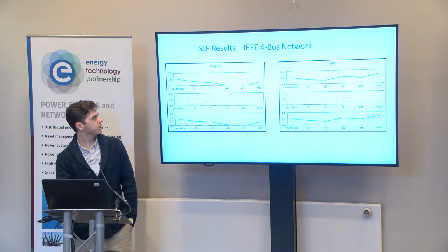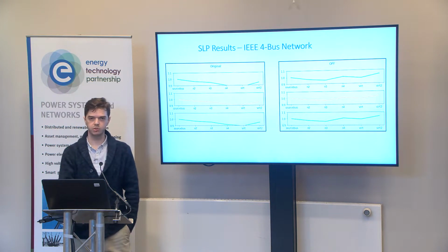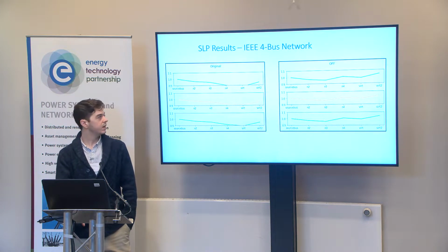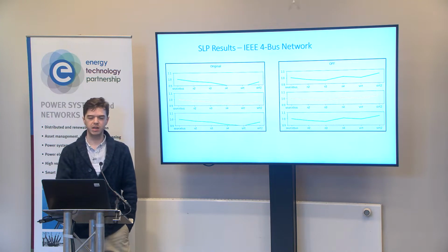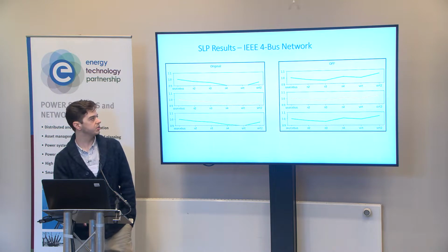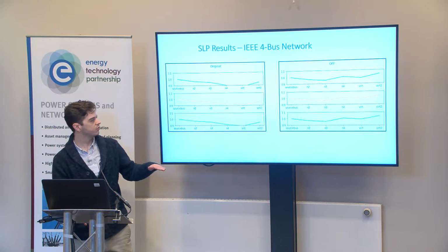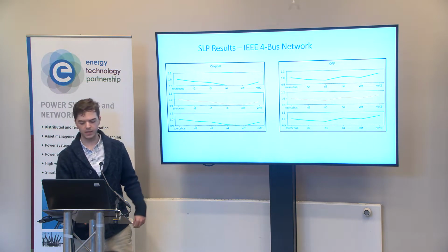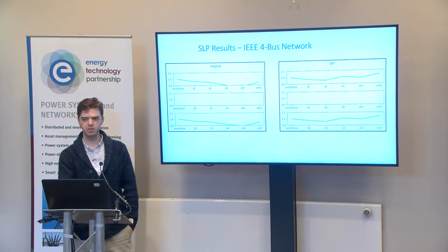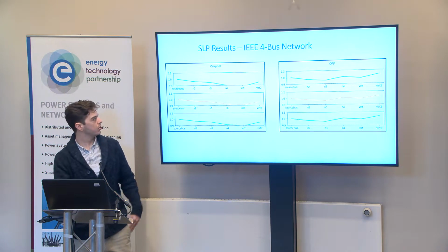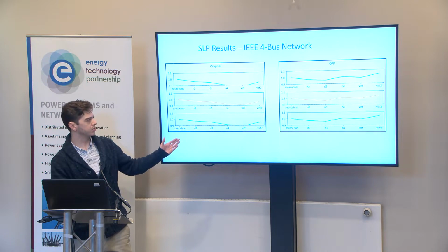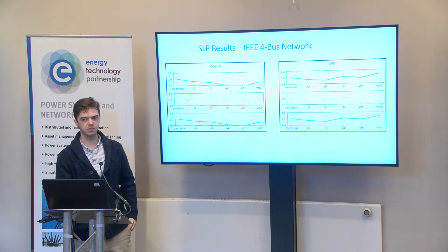Shown here are some preliminary results of the sequential linear programming method. In these cases, the method is being used to control hybrid transformers in order to achieve voltage regulation to prevent network voltages from deviating from 1 per unit. Shown here are the results for the IEEE 4-bus network, where on the left we have the network without hybrid transformer compensation and on the right with compensation.